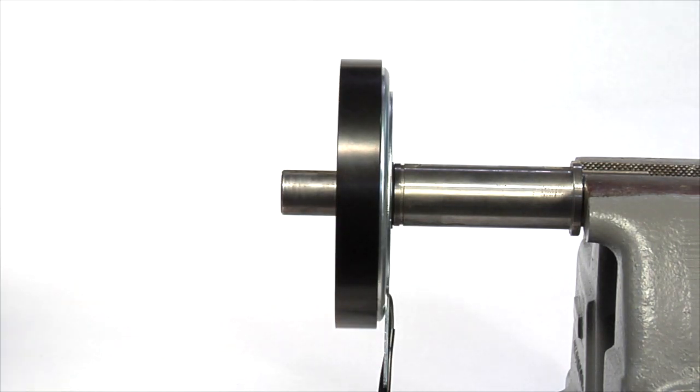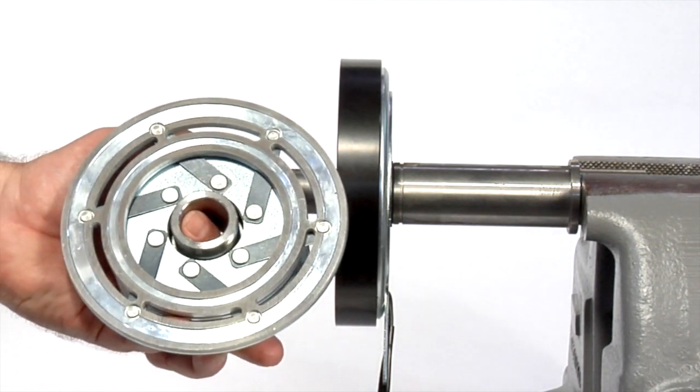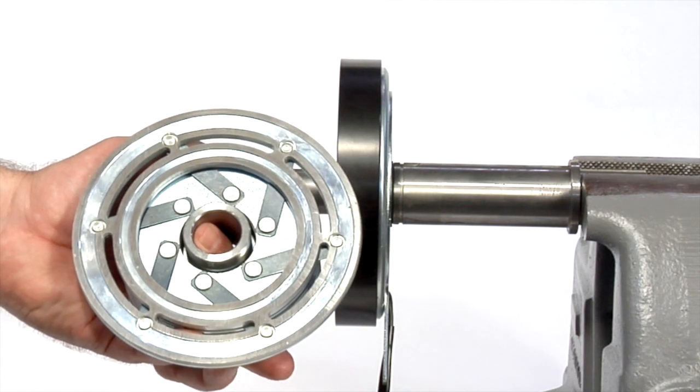General purpose clutches are unidirectional. Clutches should be mounted so that the springs are pulling on the armature. The clutch shown operates counterclockwise.